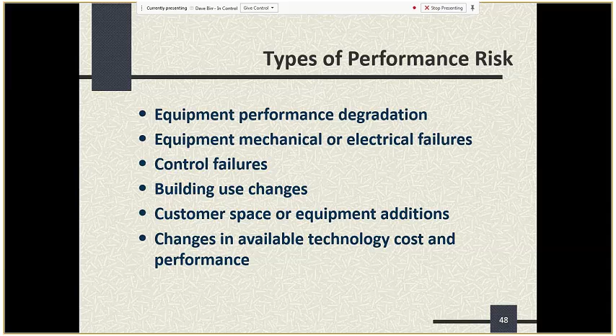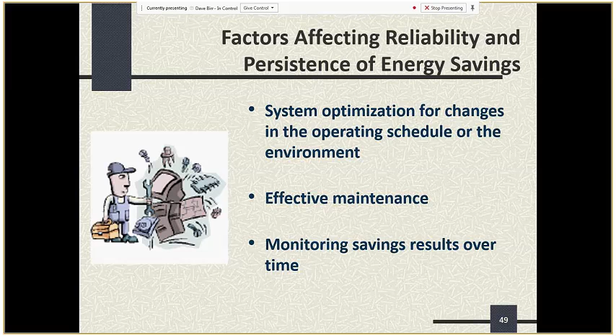What are some of the factors that affect reliability and performance over time? There's system optimization for changes in the operating schedule or environment. You can face a new load, but if you reconfigure the chiller to optimize for that new load, you can still maintain the best savings. But if you keep running with the same sequence of operations, that may not be optimal, and you may not get the savings you hope for. Also, monitoring savings over time, as JCI is doing—particularly on the PV system, the ventilation fans, and the chiller system—is a very important source of future value that you want to be tracking.